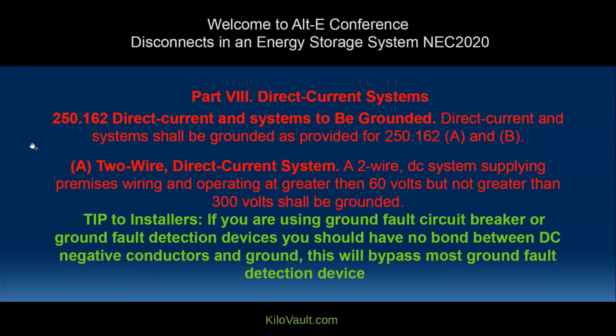So, getting a little more into what's going to be required at this point. Direct current shall be grounded as provided in 250.162 A and B. A is the crucial one we want to look at here. A 2-wire DC system supplying premises wiring and operating at greater than 60 volts, keyword greater than 60 volts here, and not greater than 300 volts shall be grounded. So if you have flooded batteries, say your charge is 300, there's a possibility that your local inspector is going to require a disconnect at this point. My little tip here at the bottom: if you're using a ground fault circuit breaker or ground fault detection device, you should have no bond between the DC negative conductor and ground. This will bypass most ground fault detection devices.